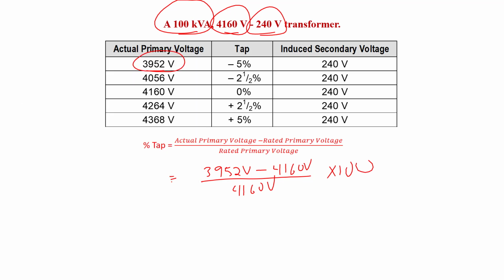So here we've got 3,952 minus 4160 equals. Notice we have a negative number there. That's why we're going to get a negative tap. So divide that by 4160, and we're at minus 0.05, so times 100, we're at negative 5%. So that's your negative 5% tap. We'd have to de-energize our transformer, set line 1 onto H1, and line 2 would go on the negative 5% tap. Let's try one of the positive values here.